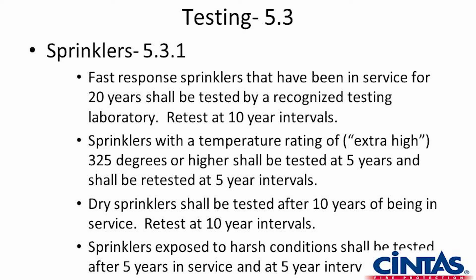We reached out to NFPA, as we do many times, to get clarification of the intent of what the developers wanted to communicate. A walk-in freezer that you would find for food preparation in a restaurant, or even maybe one of your dining kitchens, for your dining area, whatever. That's not what we're talking about. We're talking about cold storage, 20-degree storage, that type of harsh environment. Those would be tested every 5 years.